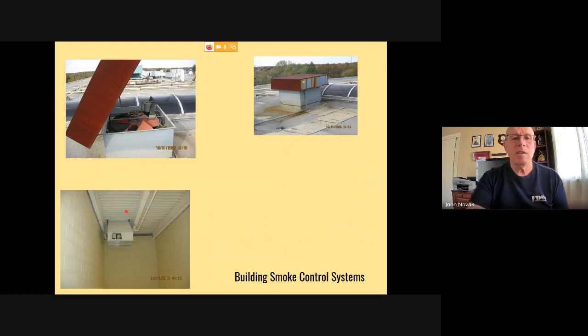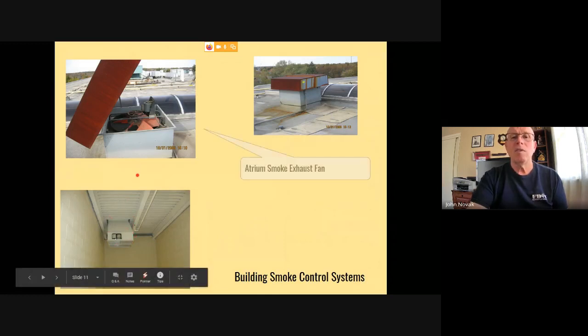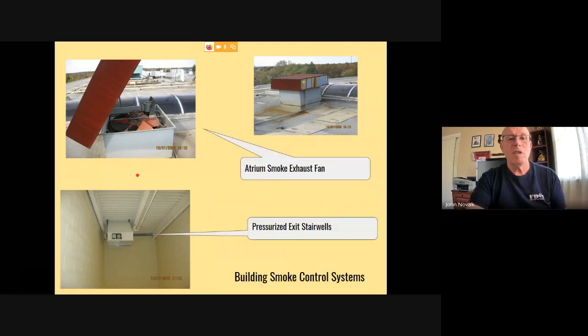Right down here we have a pressurized stairwell. So this is a fan that is sitting on top of the roof. It does have a smoke detector here. So in this case, when the smoke detector activates, this fan kicks on and pressurizes the stairwell. So the idea here is to keep the smoke out of the stairwell. And again, you can have so many X amount of doors open or ajar, and the stairwell should be kept fairly clear. So this will allow occupants to exit the stairwell. It will also give the fire department an area in which to initiate a fire attack with a standpipe.